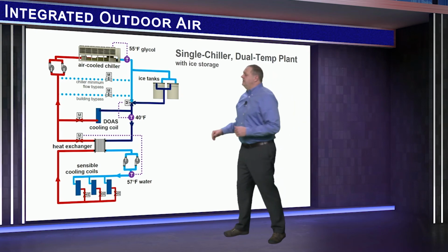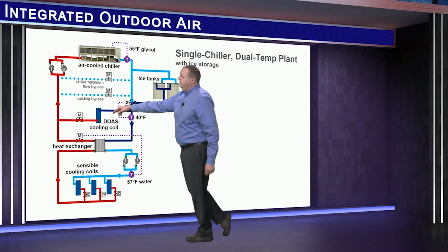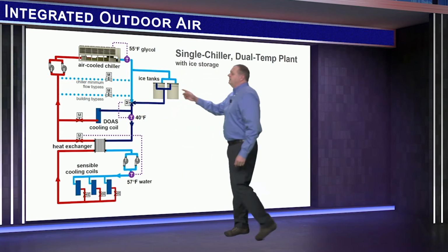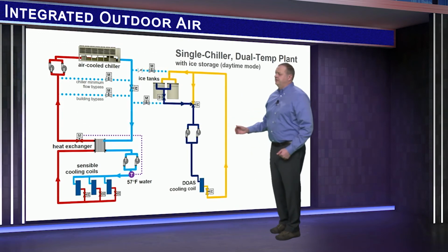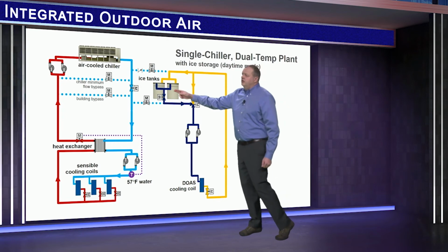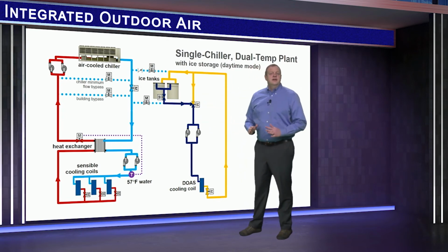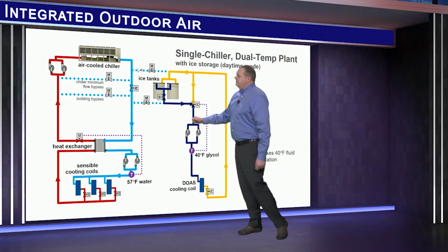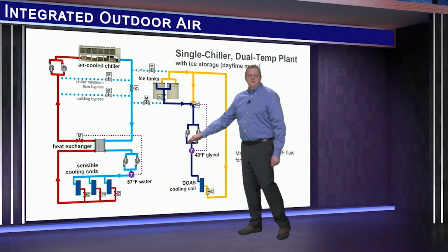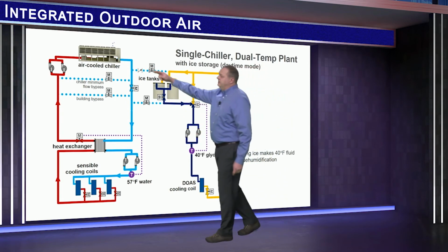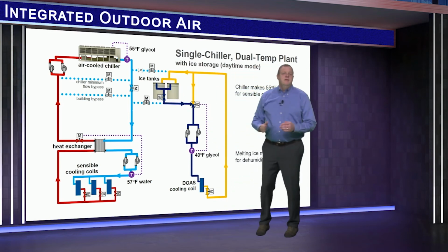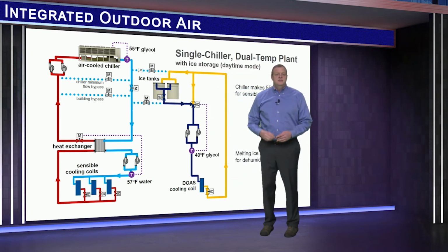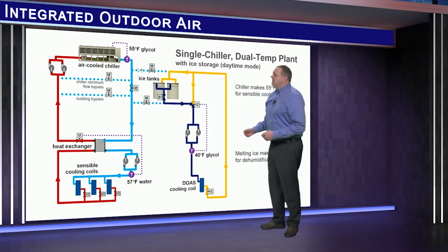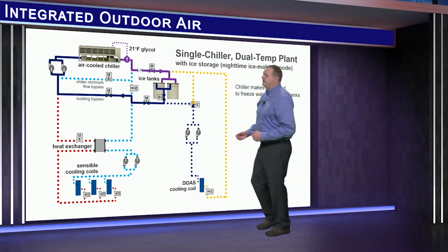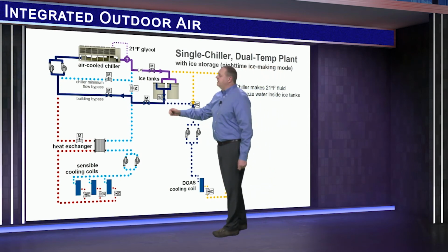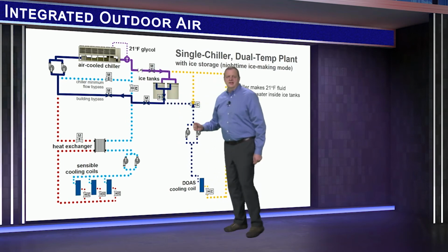The new part is to move the cooling coil in the dedicated outdoor air unit, along with this blending valve, from this loop over to a new loop with its own set of pumps. This allows the ice tanks alone to serve the dehumidification load. So during daytime operation, the ice in the tanks is melted to produce the 40-degree fluid needed for dehumidification. This allows the water chiller then to raise its set point and make warmer fluid for the sensible cooling terminals. So the chiller operates more efficiently. Then, when the building is unoccupied at night, the chiller switches to an ice-making mode, lowering its set point to refreeze the water inside the tanks for the next day.